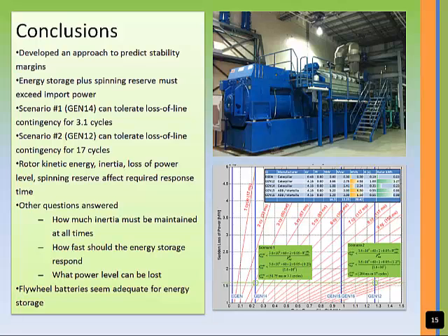The underlying assumption, however, was that the energy storage output power plus the spinning reserve must exceed the sudden power change. If the sudden step in power can be met, the generator can be stopped from decelerating and the frequency can be maintained. If there is more power reserved than is changed at once, the rotor can be stopped from decelerating and also re-accelerated back to 60 Hertz.